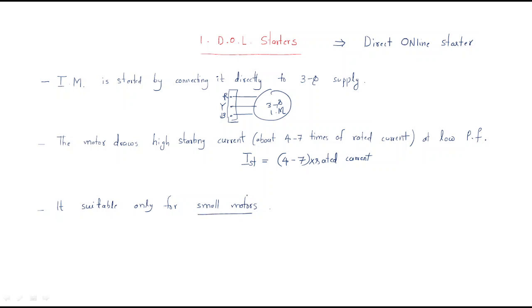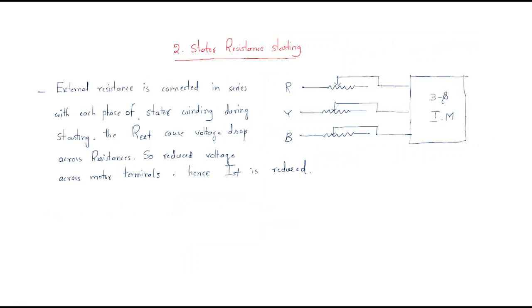For small motors, there is no requirement for these controls, so the DOL starter is suitable for small motors. The rating is up to 10 kilowatts; for motors up to this rating, the DOL starter is very useful.